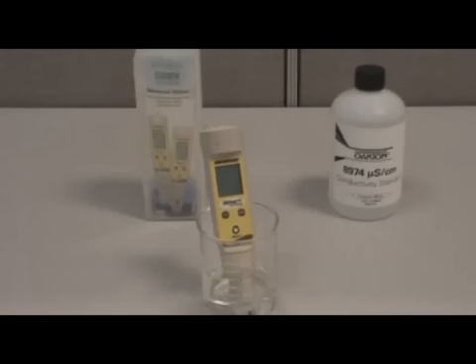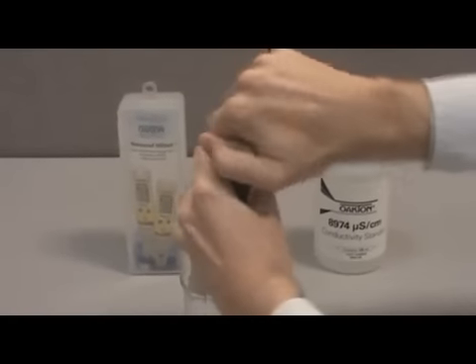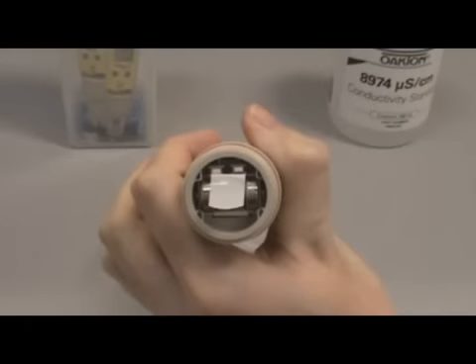Before we can begin calibration, we need to gain access to the control buttons located in the battery compartment. To do this, grip the tester firmly in one hand and twist off the battery cap in a counter-clockwise direction. Be sure to retain the O-ring located underneath the cap. You can now see the increase and decrease buttons along with the batteries.